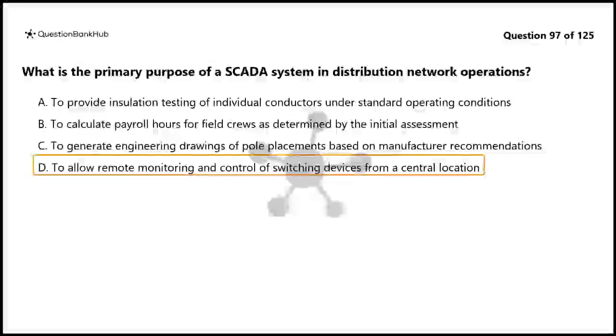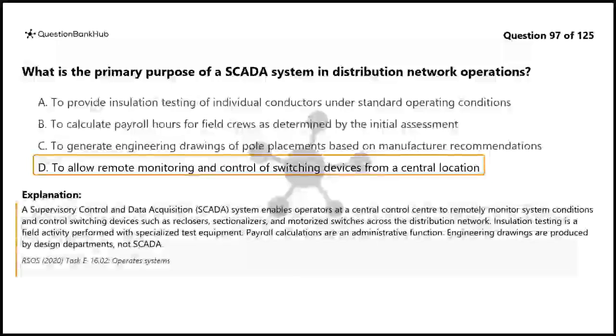The correct answer is D. A supervisory control and data acquisition (SCADA) system enables operators at a central control center to remotely monitor system conditions and control switching devices such as reclosers, sectionalizers, and motorized switches across the distribution network. Insulation testing is a field activity performed with specialized test equipment. Payroll calculations are an administrative function. Engineering drawings are produced by design departments, not SCADA.